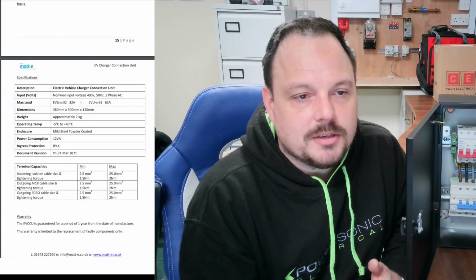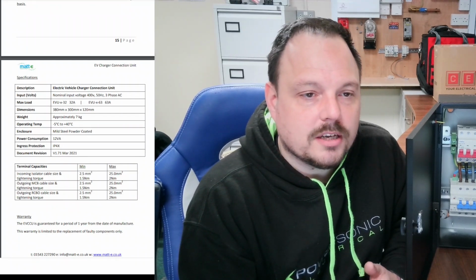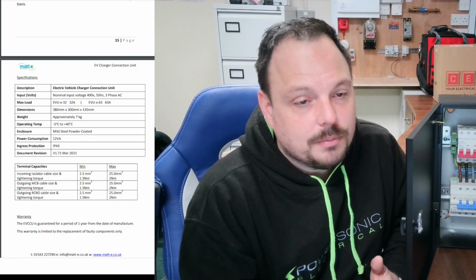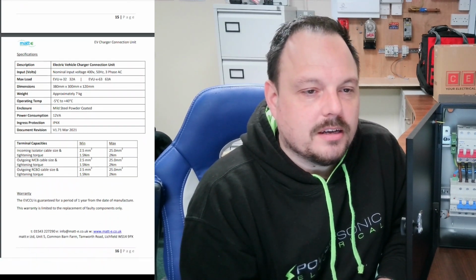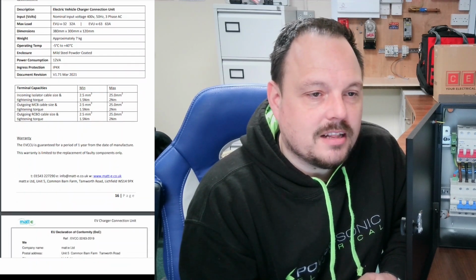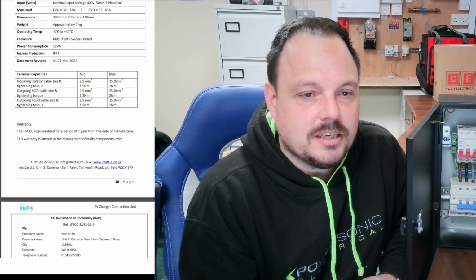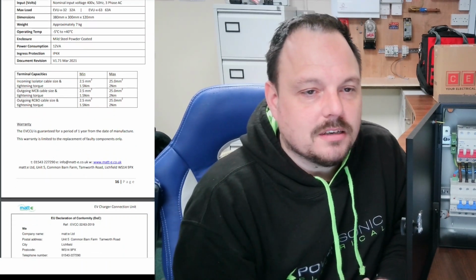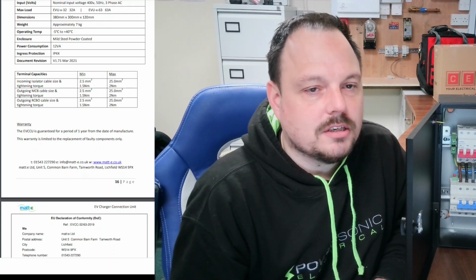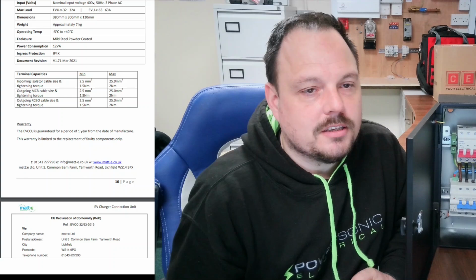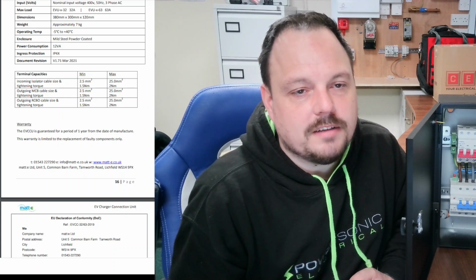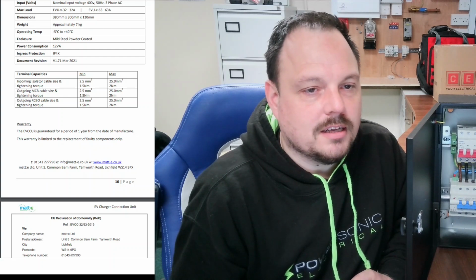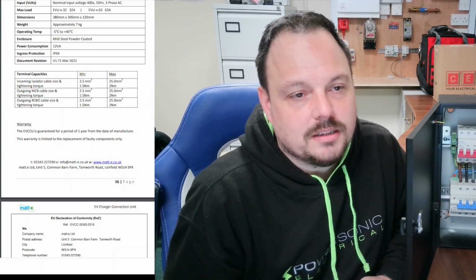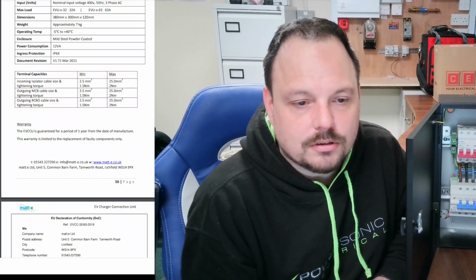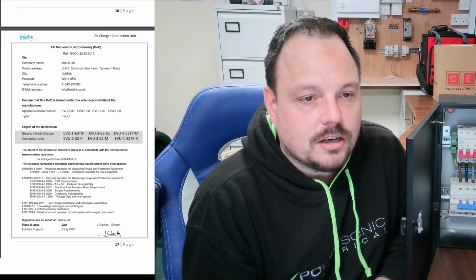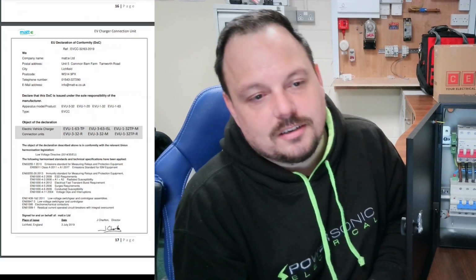So then it gives you all of the parameters for this charge point, the voltages that it will work to, the loadings, its dimensions, its weight, the operating temperature, it's always a factor. The power consumption, its IP rating, and then the all-important torque values. So you can see there, they give a minimum and maximum of the tightening torque on these products. And you can see there, if you're using 2.5 mil, it's 1.5 newton meters. And then if you're using 25 mil, it's 2 newton meters. And then there's the same sort of differential between the MCBs and the RCBOs and such, depending on the product that you're using.